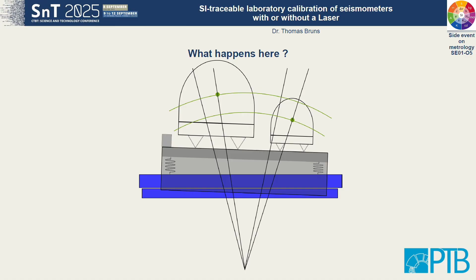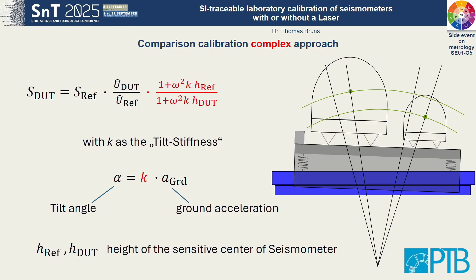If you knew this height of the sensing element, or of the sensitive center of the instrument, you can correct for it. So this simple equation that I introduced before gets a correction factor. And here we made an approximation that the tilt angle alpha is proportional to the acceleration, because it's an effect that happens due to inertial effects. The mass times acceleration gives you a torque on the tilt table, on the shaker table. It's not supposed to be a tilt table, but it is in this case. We applied a constant there because we looked at the tilt in terms of amplitude of acceleration, and it had a very nice linear behavior. That's the background for that.